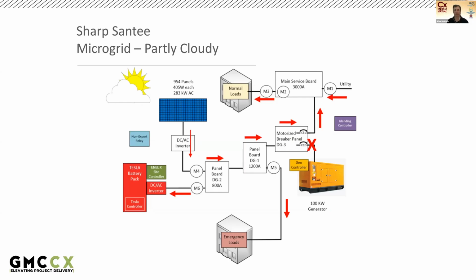So now let's say clouds come in and block the sun a little bit. Power from the solar array still supplies power to DG2, which can still charge the Tesla battery, supplies power to DG1, sending power to the emergency loads, and sending power back up to the main service board. Maybe there's a little bit more to serve the normal loads, but not enough. In that case, we're bringing power in from the utility just to offset any additional power that we will need.